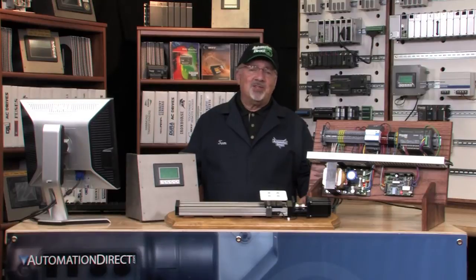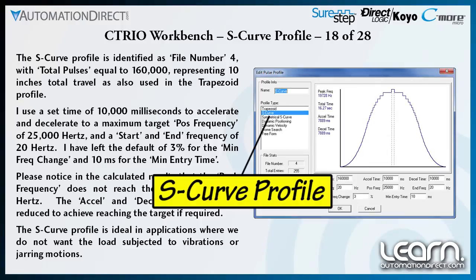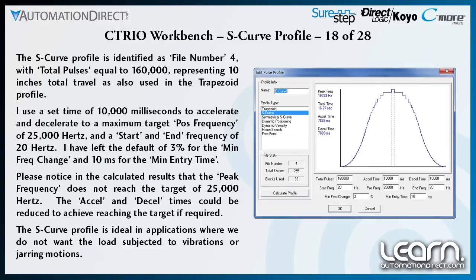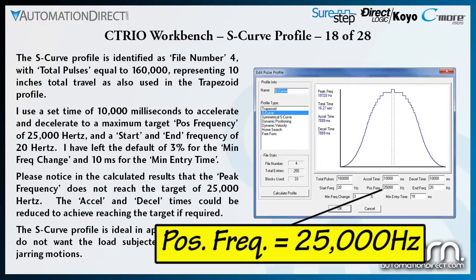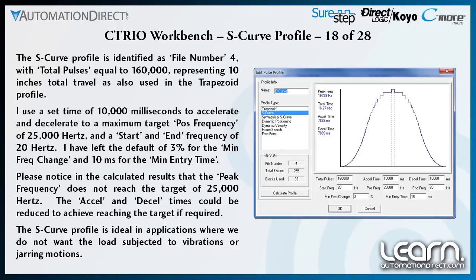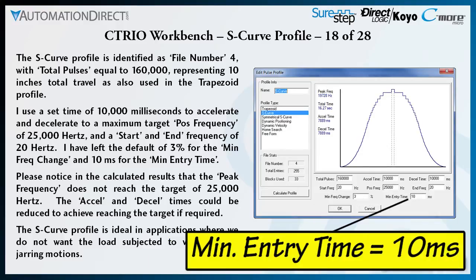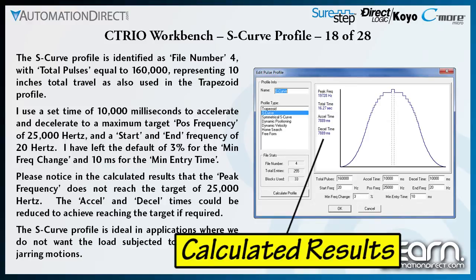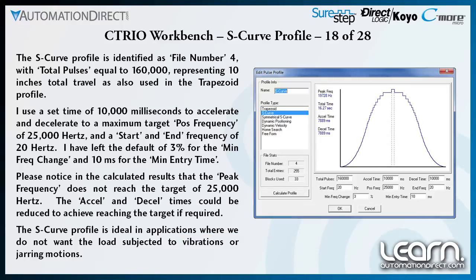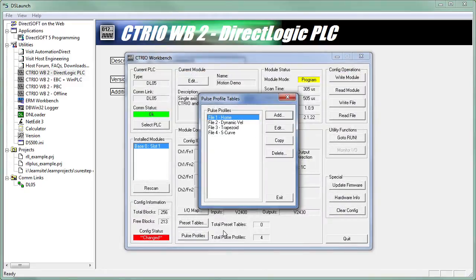The second predetermined move profile is the S curve profile, identified as file number 4. Like the trapezoid profile, the total pulses is set to 160,000 steps, representing 10 inches of total travel. I use a set time of 10,000 ms to accelerate and decelerate, and a maximum target POS frequency of 25,000 Hz. The start and end frequency is set to 20 Hz. I have left the default of 3% for the min frequency change and 10 ms for the min entry time. Notice that the peak frequency does not reach the target of 25,000 Hz in the calculated results. The S curve profile is ideal in applications where we do not want the load subjected to vibrations or jarring motions. I click OK to add the new profile to my table.